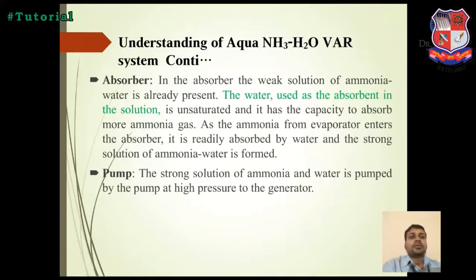Absorber: points 1, 2 and 3 are there, with 2 as inlets and 1 as outlet. At the inlet, the weak solution from the generator comes into the absorber, and the NH3 vapor coming from the evaporator is mixed in the absorber to create a strong solution. This strong solution is pumped by the pump into the generator for smooth working of the cycle.